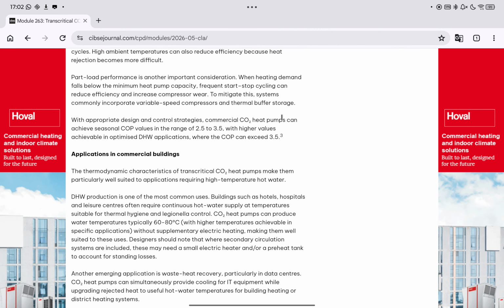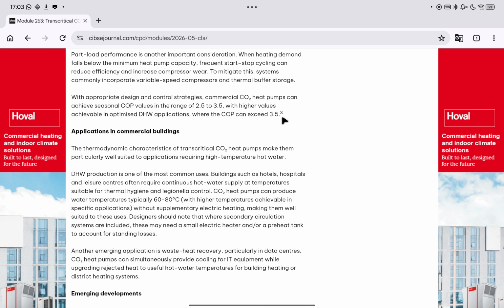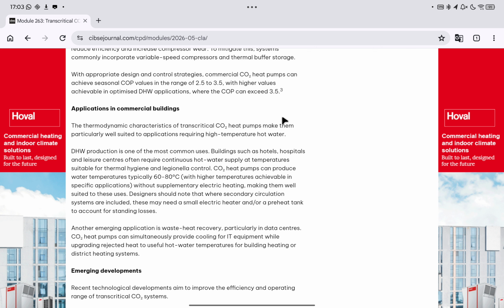Applications in commercial buildings. The thermodynamic characteristics of transcritical CO₂ heat pumps make them particularly well suited to applications requiring high temperature hot water. DHW production is one of the most common uses. Buildings such as hotels, hospitals and leisure centres often require continuous hot water supply at temperatures suitable for thermal hygiene and Legionella control. CO₂ heat pumps can produce water temperatures typically 60 to 80 degrees C, with higher temperatures achievable in specific applications, without supplementary electric heating, making them well suited to these uses. Designers should note that where secondary circulation systems are included, these may need a small electric heater and/or a preheat tank to account for standing losses.